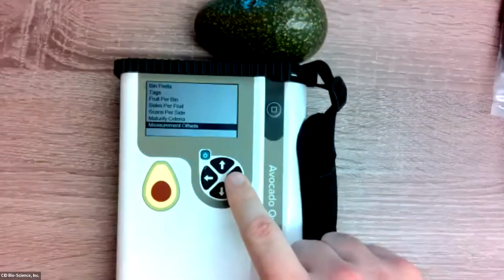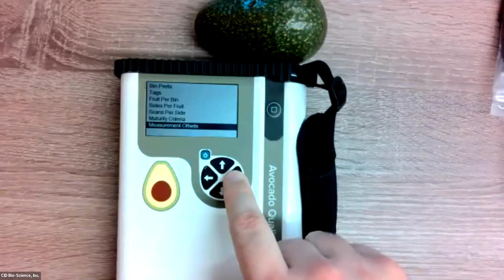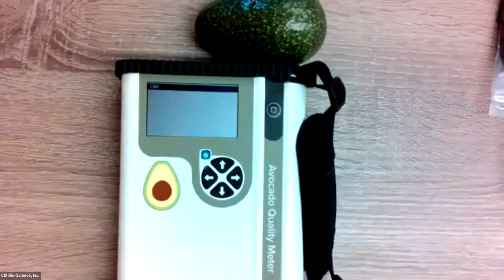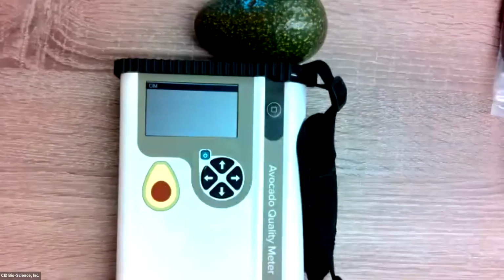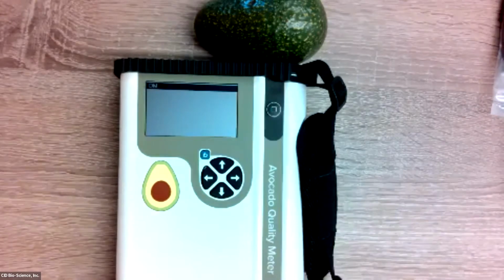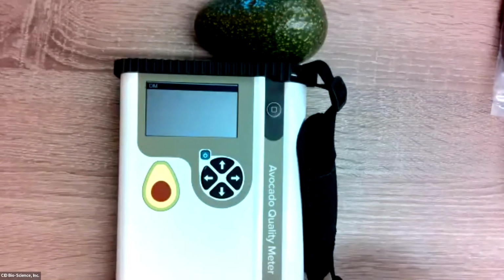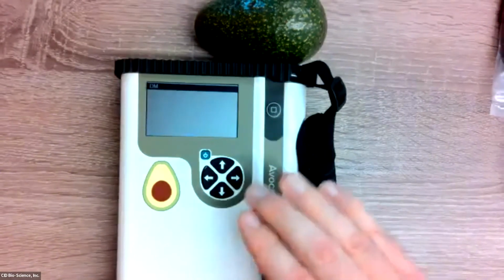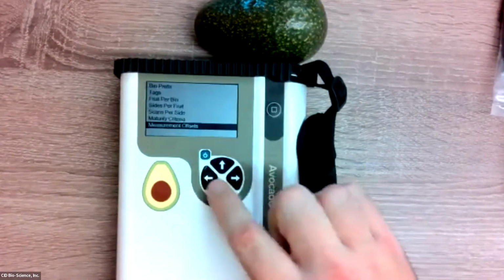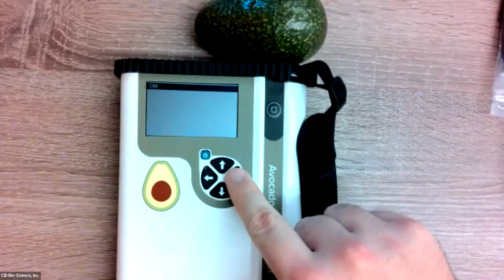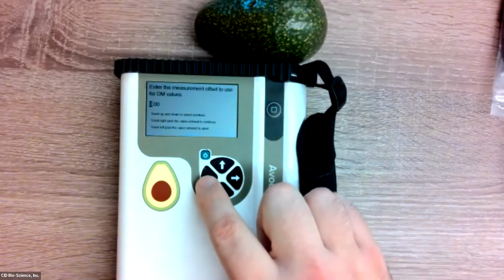The last thing I want to discuss quick is this measurement offset feature. As I mentioned, we have this coring tool that comes with the device. In some cases, you might find that the instrument needs to be calibrated so that it reads more accurately to your fruit. And in those cases, you typically need to set an offset, which is just a bias correction for the data so that it aligns more correctly with your current analytical method. So to enter that value, you simply have to go into this measurement offset, dry matter, and then you can enter the offset value here.